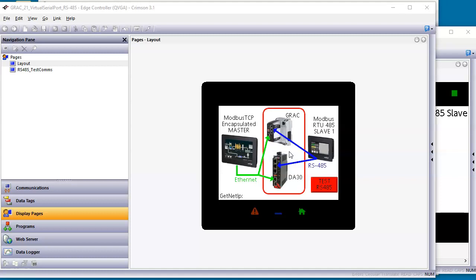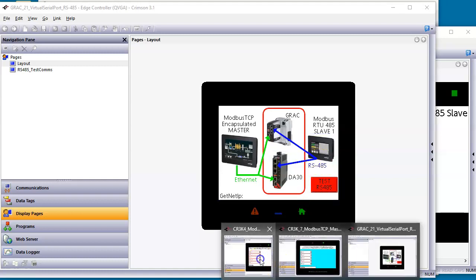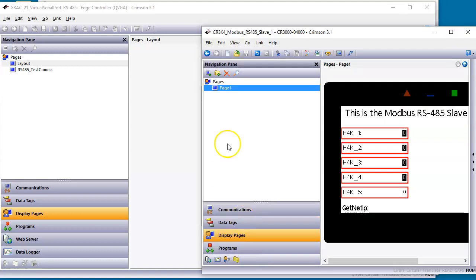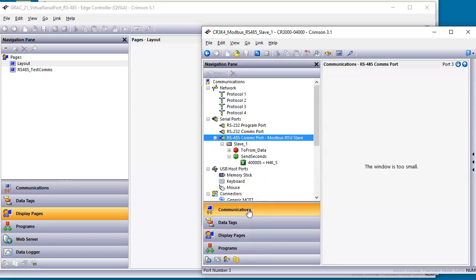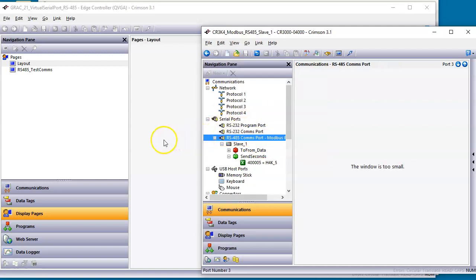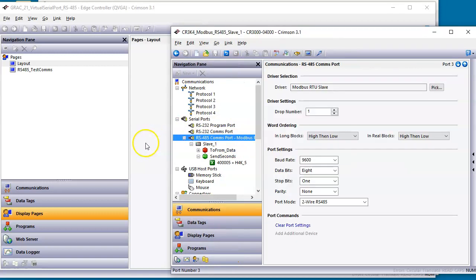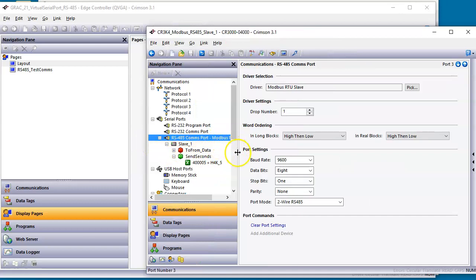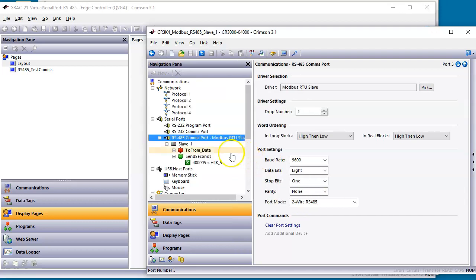In this case, I've got the GRAC in the middle set up here, and I got this 4-inch over here acting as a slave. So let me just show you first the slave configuration. Here's the program that's running in my 4-inch screen acting as a slave. I've got on it the RS-485 port set up as a Modbus slave. Let me make this a little bigger so you guys can see this. I've got this guy set up as a Modbus slave, 9600, 8, 1, and none, using RS-485, standard settings there.